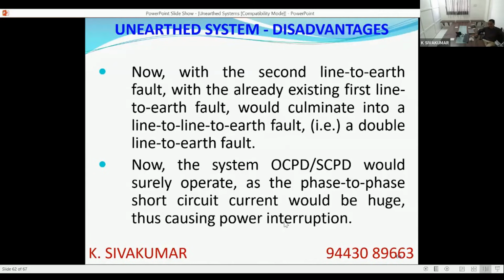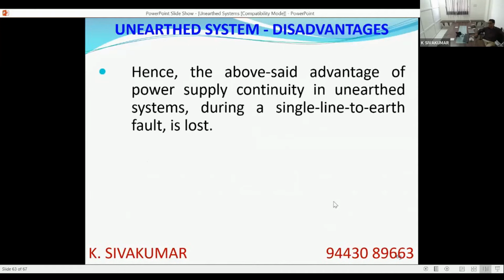So whatever we told initially for understanding, that the advantage of an ungrounded system is that no interruption is lost, that advantage is lost. Because a single line to ground fault will never remain a single line to ground fault, it will soon culminate in a second line to earth fault, ending up as a double line to ground fault. This line to line fault current is more, and the breaker trips or the fuse will blow, causing interruption. So that advantage is definitely lost.